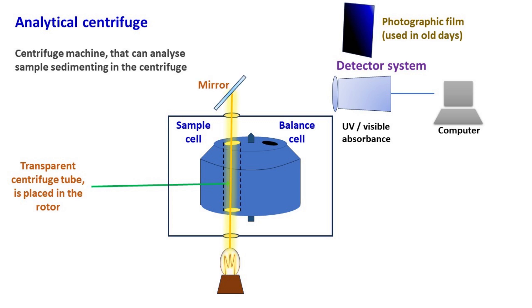The top of the centrifuge chamber has a mirror that reflects light to the detector system. The detector system can measure the absorbance of UV or visible light. Besides UV and visible light, it can also detect changes in the refractive index of the sample.